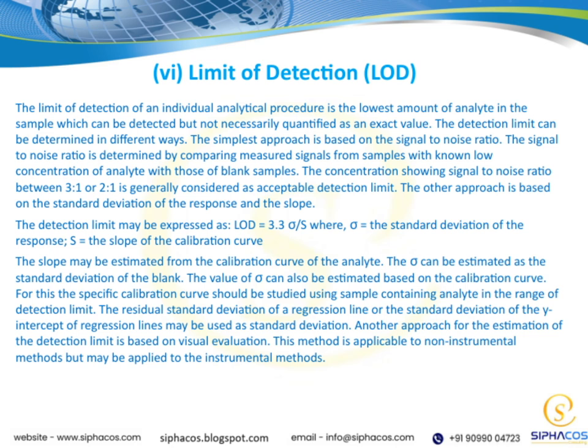Another way involves looking at the standard deviation of responses and the slope of the calibration curve. Here, the detection limit can be expressed mathematically as LOD equals 3.3 times sigma divided by S, where sigma is the standard deviation of the response and S is the slope of the calibration curve. To estimate the slope, we typically use the calibration curve generated from samples with known analyte concentrations.